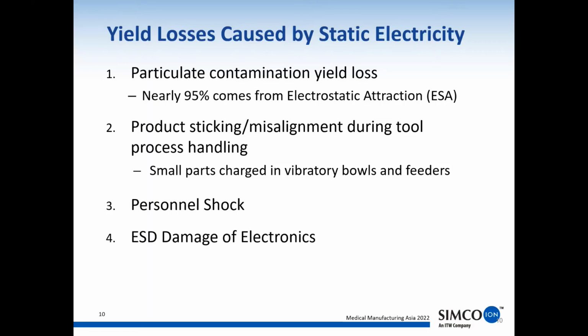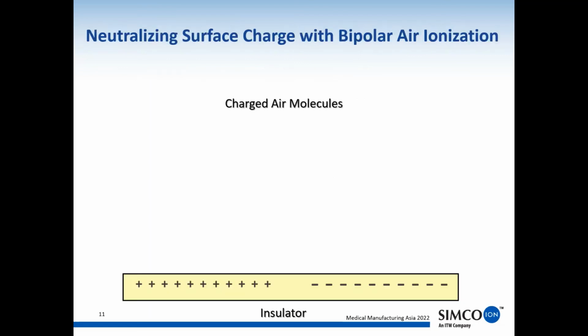There's also ESD damage of electronics. The ESD Association has been involved in this for 40 years, trying to control ESD damage for electronic materials. This is starting to rear its ugly head in medical devices too, because many electronic pacemakers, defibrillators, neuromodulation devices, and similar products have electronics that are becoming more and more sensitive to ESD damage. So this is becoming a more critical problem. The advantage is, if we can control the static electricity, we can control all of these things.